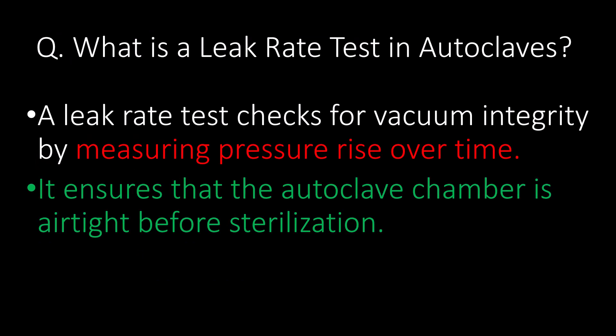A very important question: what is a leak rate test in autoclaves? A leak rate test checks for vacuum integrity by measuring pressure rise over time. It ensures that the autoclave chamber is airtight before sterilization.